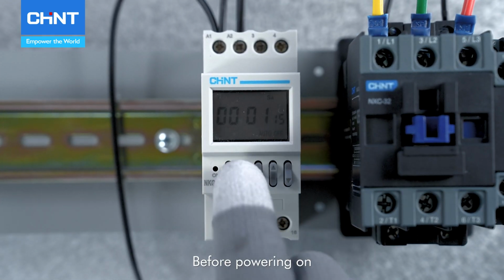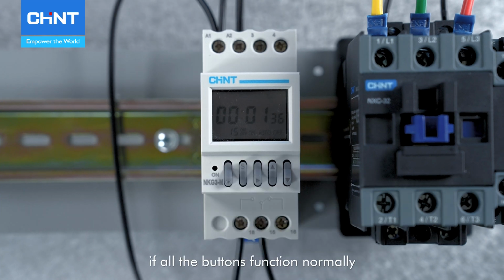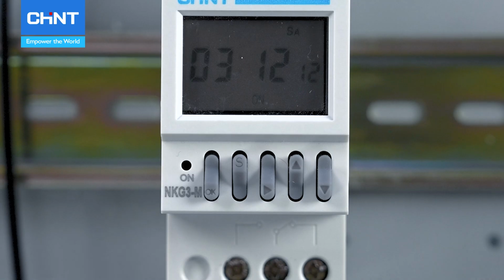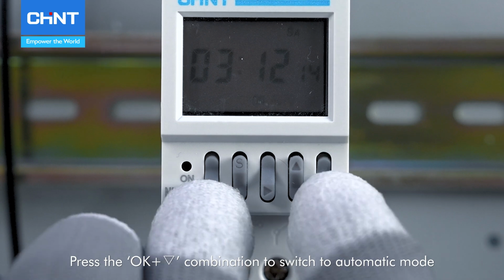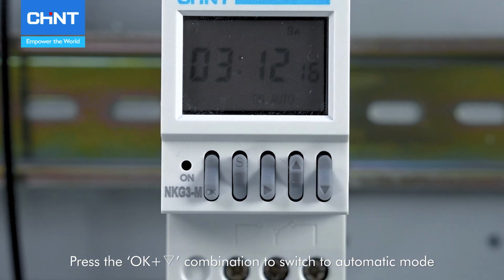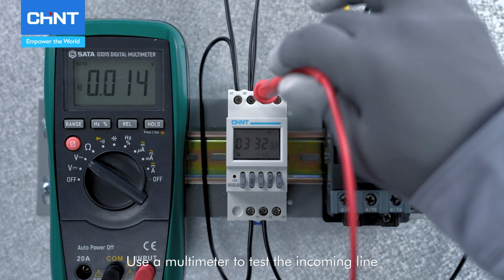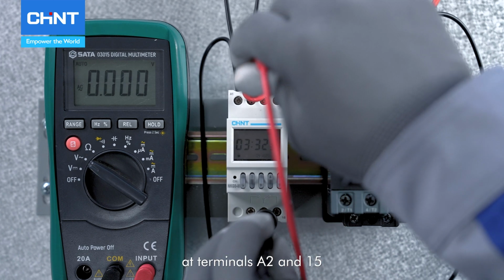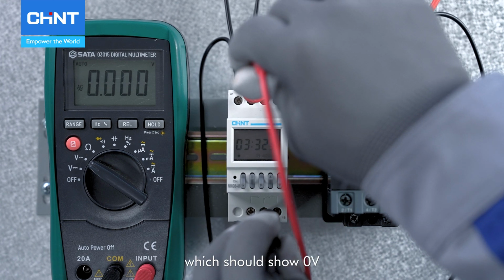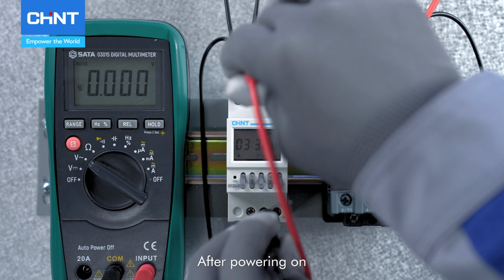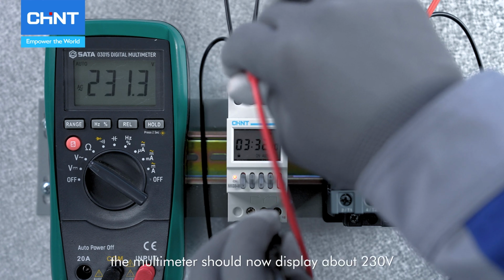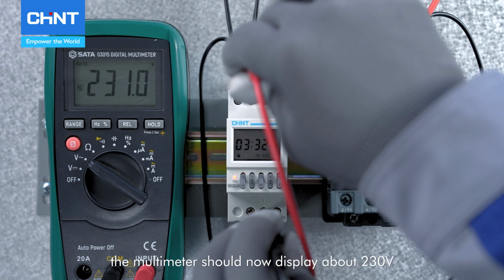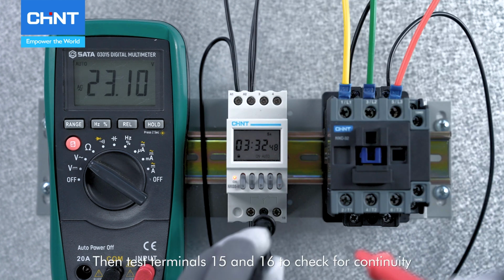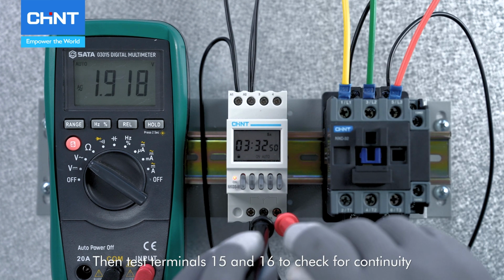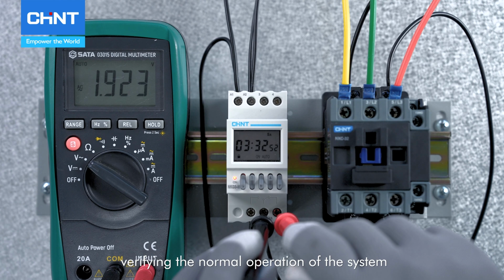Before powering on, follow the instructions to check if all the buttons function normally. Press the OK plus down combination to switch to automatic mode. Use a multimeter to test the incoming line at terminals A2 and 15, which should show 0 volt. After powering on, the indicator light turns on, and the multimeter should now display about 230 volts. Then test terminals 15 and 16 to check for continuity, verifying the normal operation of the system.